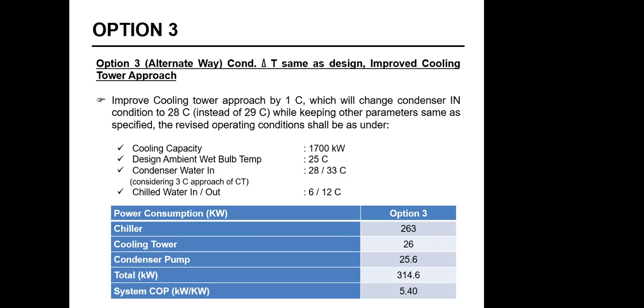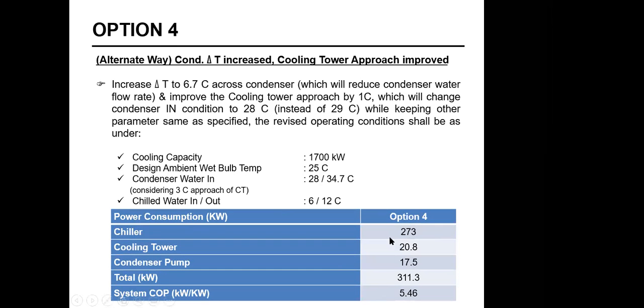Now, next option. We apply one more alternate. How can we improve it further? We did the same thing, but in this case, instead of increasing the delta T, we have reduced the approach of the cooling tower from 4 degrees centigrade to 3 degrees centigrade. What happens with that change? The rest of the parameters remain the same. My power input again changes, and my system COP is 5.4. Then one more alternate option we applied, where we mixed option 2 and option 3. We reduce the approach to 3 degrees centigrade, and we increase the condenser water temperature delta T to 6.7. With this, again, a set of readings has come, with the power consumption of the system and the COP.